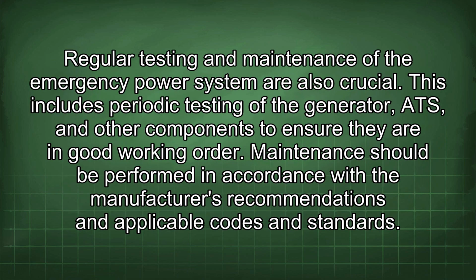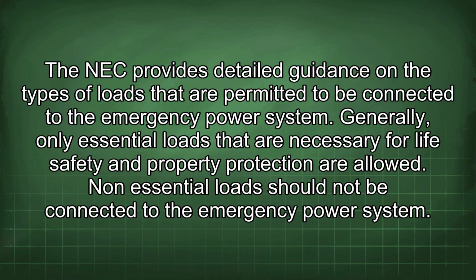Regular testing and maintenance of the emergency power system are also crucial. This includes periodic testing of the generator, ATS, and other components to ensure they are in good working order. Maintenance should be performed in accordance with the manufacturer's recommendations and applicable codes and standards. The NEC provides detailed guidance on the types of loads that are permitted to be connected to the emergency power system. Generally, only essential loads that are necessary for life safety and property protection are allowed. Non-essential loads should not be connected to the emergency power system.